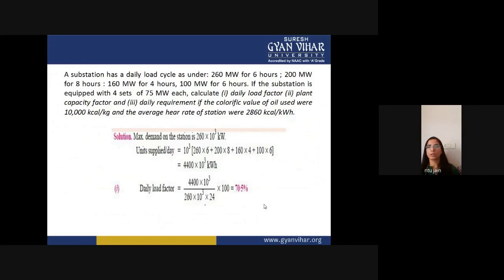So this is very important: the problem gives a load cycle in which 260 megawatt is required for 6 hours, 200 megawatt for 8 hours, and 160 megawatt for 4 hours. So you can calculate the units generated by the substation. Units supplied per day is 260 into 6 plus 200 into 8 plus 160 into 4 plus 100 into 6. So you will get 4,400 into 10 to the power 3 kilowatt hour. This is the unit supplied per day.